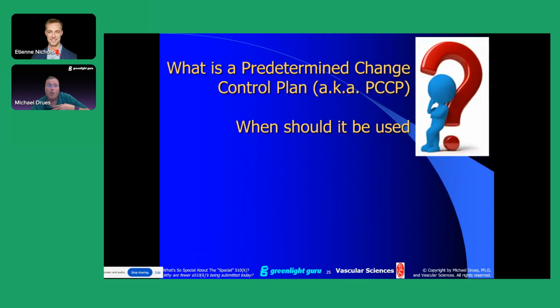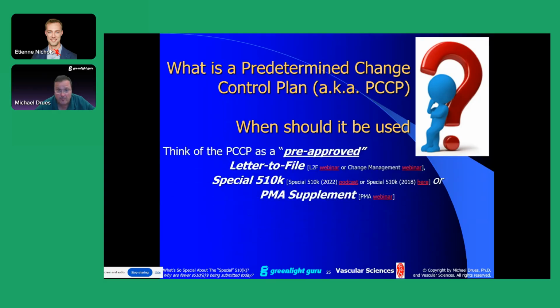Something to think about. So what is a PCCP and when should it be used? Again, this is described in much more detail in my PCCP webinar, but in a nutshell, you can think of a PCCP as a pre-approved letter to file or special 510K or PMA supplement. In other words, the way it works now is you put a device on the market, and then if you want to make a change to that device, you usually, underline usually, notify the FDA with either a special 510K or a PMA supplement. But now we have another option.